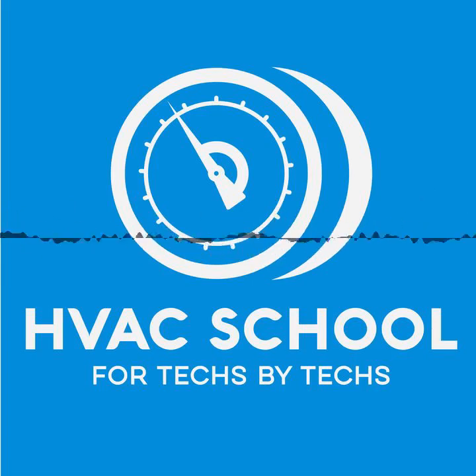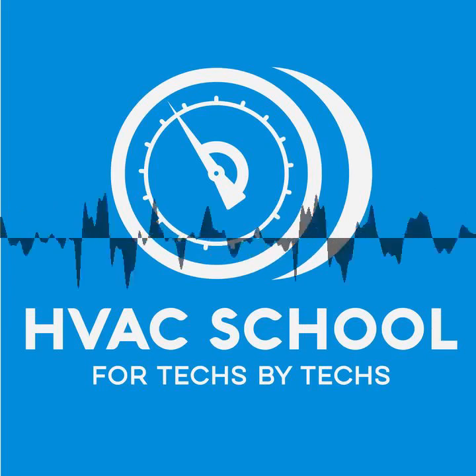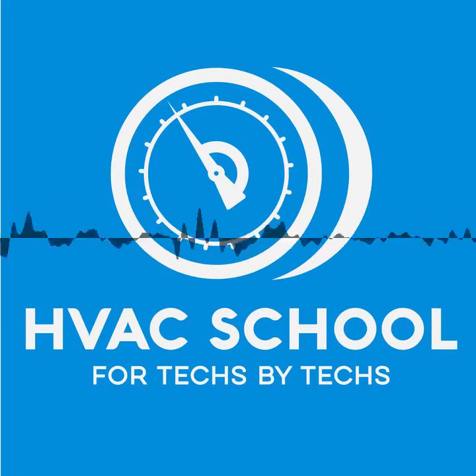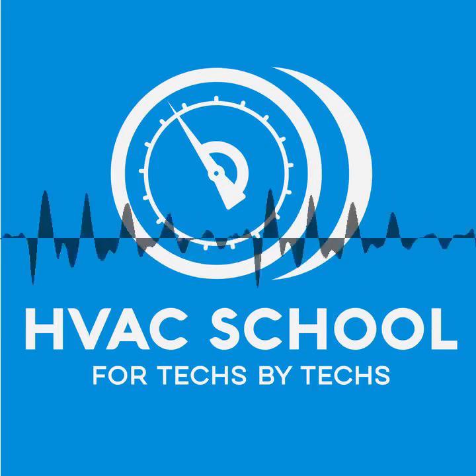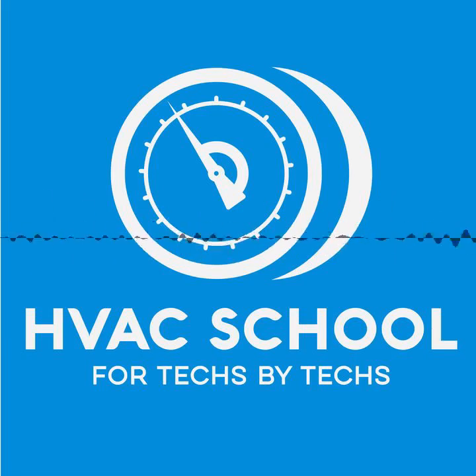And we got that heat energy down to a minimum. We're condensing as much of the moisture in the secondary heat exchanger as we can. We can't condense 100% of it. We have some of the exhaust gas coming out the side of our house as a little cloud, just like it's a dryer vent. And we've now changed the draft inducer motor from a metal one to a plastic one because A, lower temperatures, but B, corrosion resistance. Because flue gases also contain acids, primarily because of chemicals in your home.